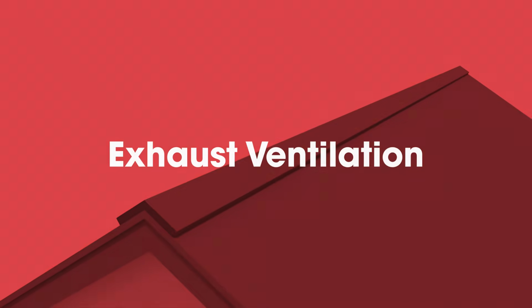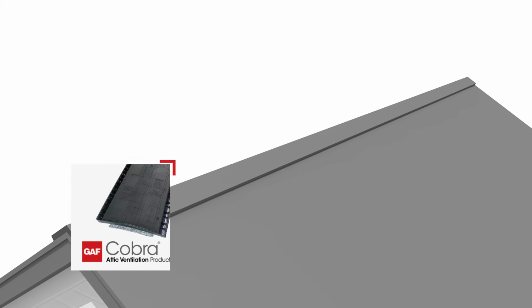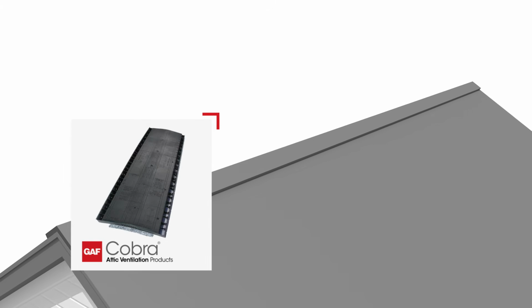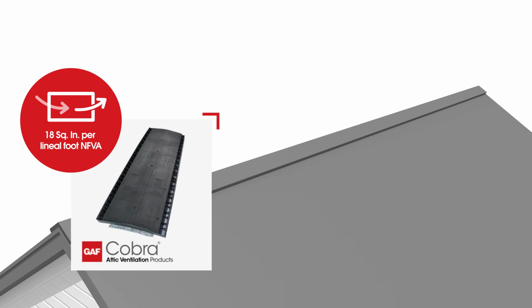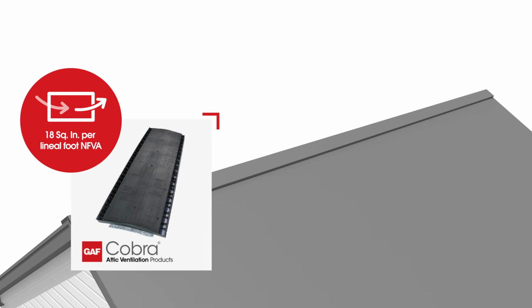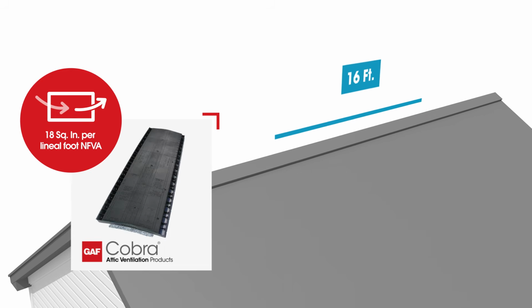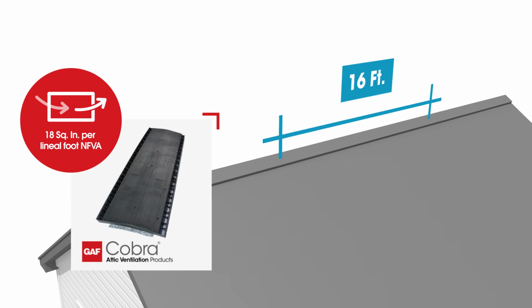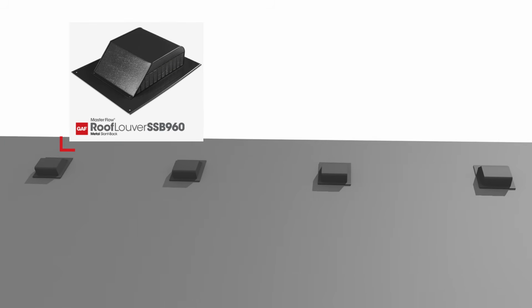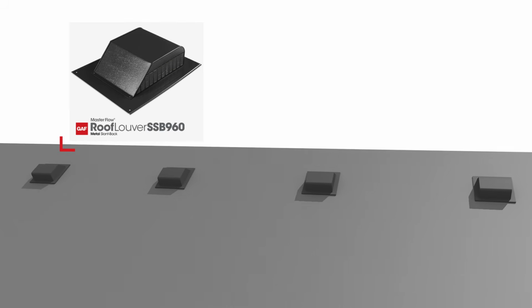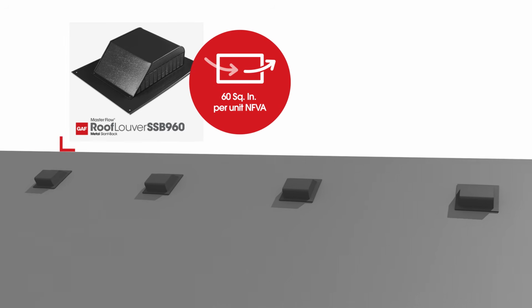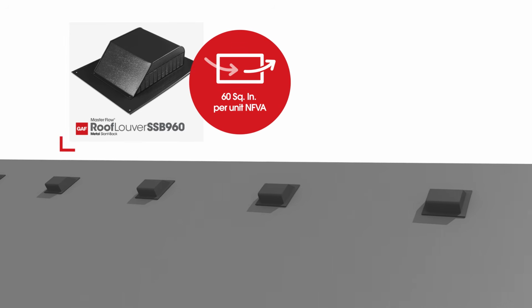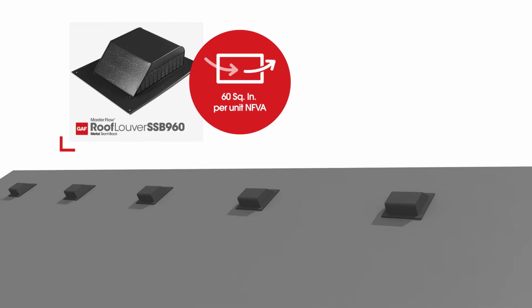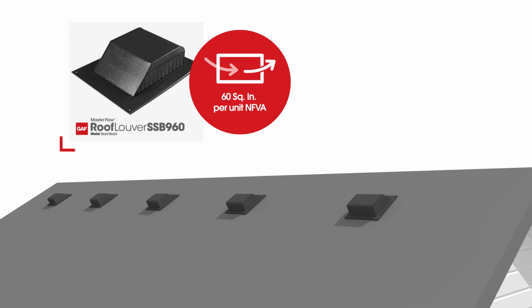Exhaust ventilation. The same approach applies to determining the amount of exhaust ventilation product you will need. If we use a Cobra 4-foot plastic ridge vent, it has an NFVA of 18 square inches per lineal foot. Therefore, we will need 16 linear feet of venting to meet the minimum exhaust ventilation requirement. But if we use MasterFlow SSB 960 slantback metal roof louver, each unit has an NFVA rating of 60 square inches. So we need 5 vents to reach the minimum NFVA exhaust ventilation requirement of 288 square inches for this attic.